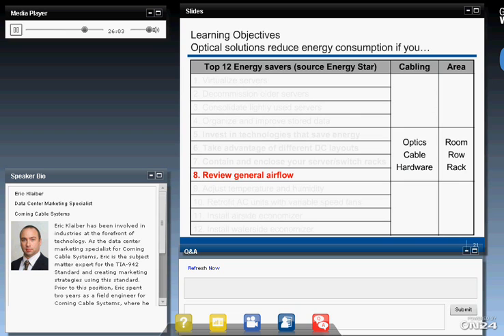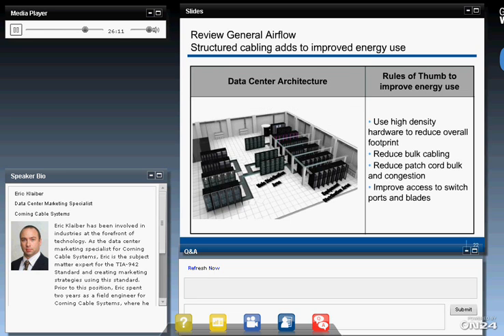Last one is the review of general airflow. So when we look at this, what we really want to do is use high-density hardware to reduce the overall footprint. The denser you go, the smaller area you have to cool. So typically you put the CRAC units on the walls, and you pump the air, and you have to be able to pump it fast enough and with enough air velocity to get to the furthest point that needs to be cooled at the temperature that it needs. So by going to a more dense footprint, you're able to reduce that overall total footprint and use smaller CRAC units. You want to reduce the bulk cabling. You want to reduce the patch cord bulk in front of and between switches. And then you need to improve the access to the switch ports and blades so that even those can get sufficient air.